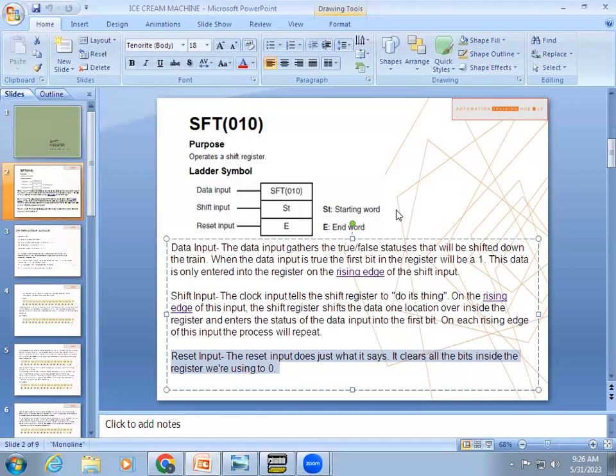In the shift register you have two address parameters: starting word and end word. You can't always shift with only 16 bits — sometimes you need more. For example, if the starting word is W0 and the end word is W2, the shifting will take place across W0, W1, and W2 — that is three sets of 16 bits, totaling 48 bits. Once the first 16-bit register is completed it moves to the second, then the third. Once the third 16-bit register is completed, that value will be erased.